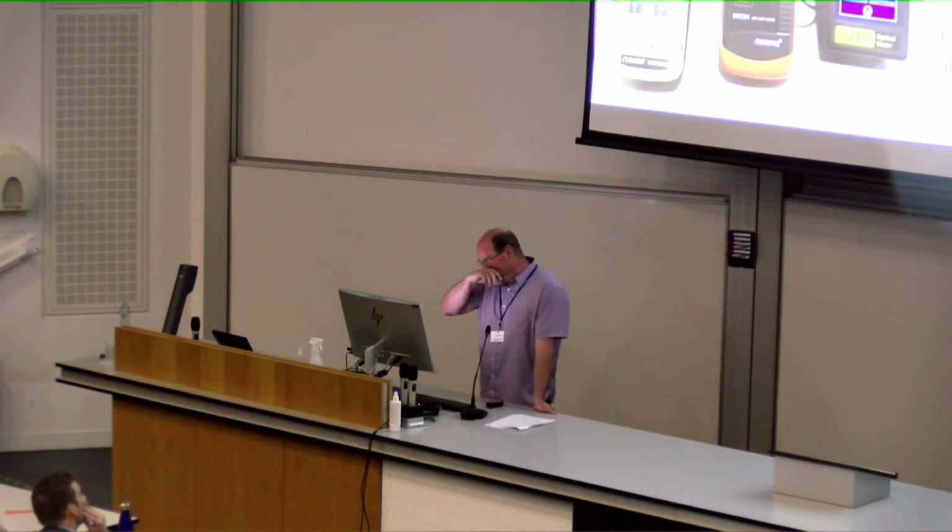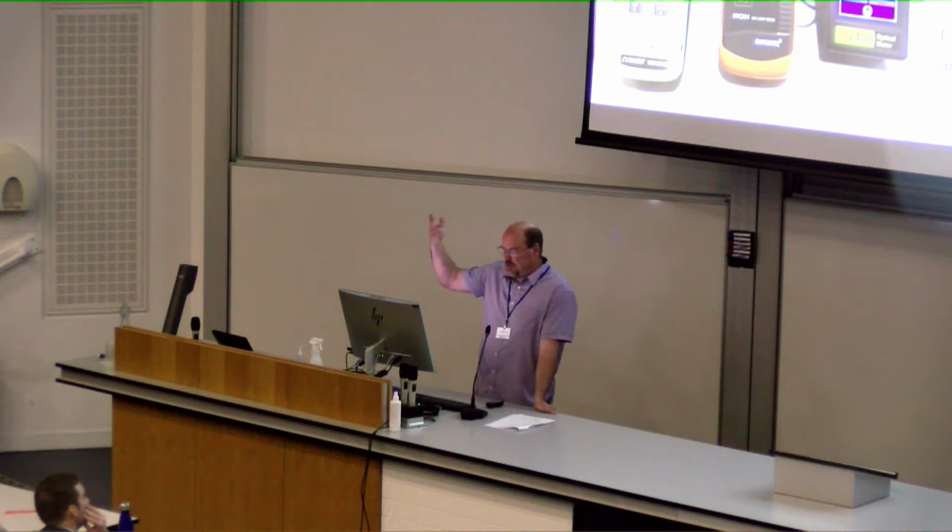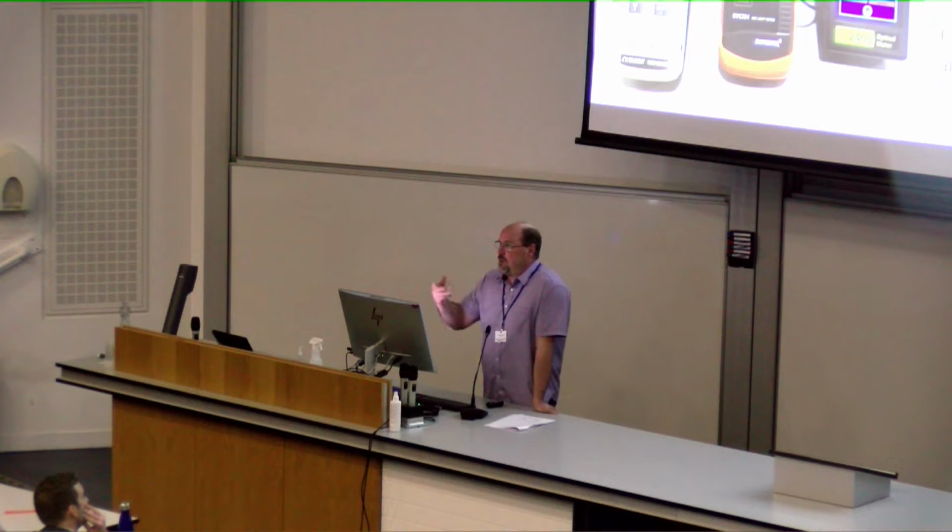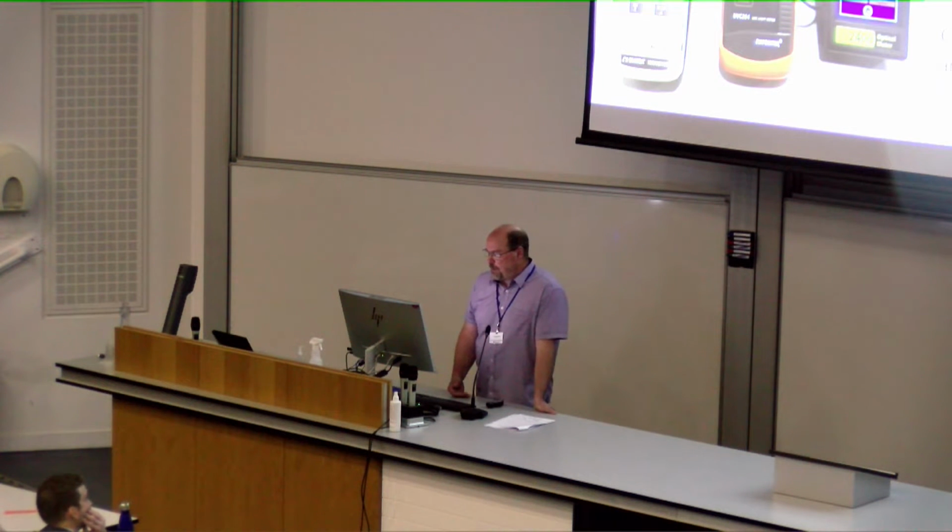For this particular case, a lot of it is that the devices are calibrated in a collimated beam, where it's going one direction. But now I've put it in an area where it's seeing photons from every direction. And that's not necessarily how the device was created to measure the photons.